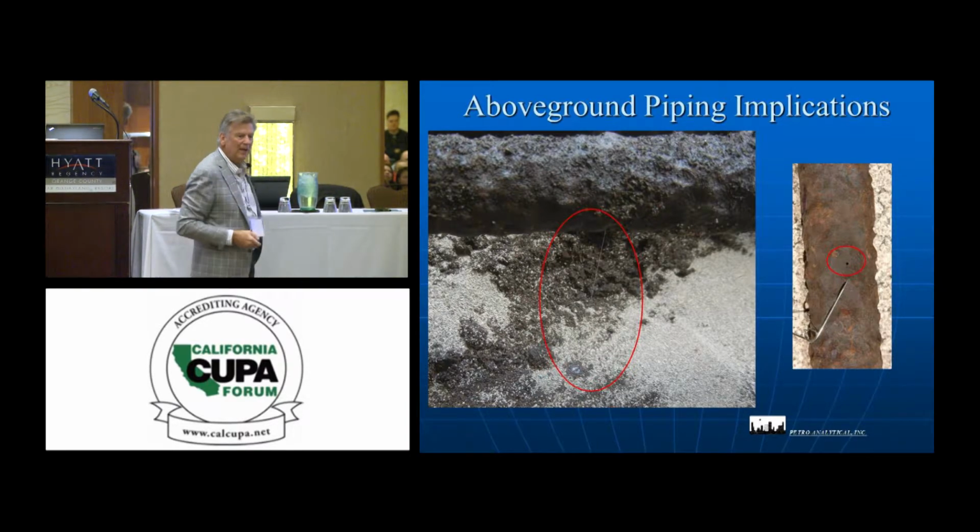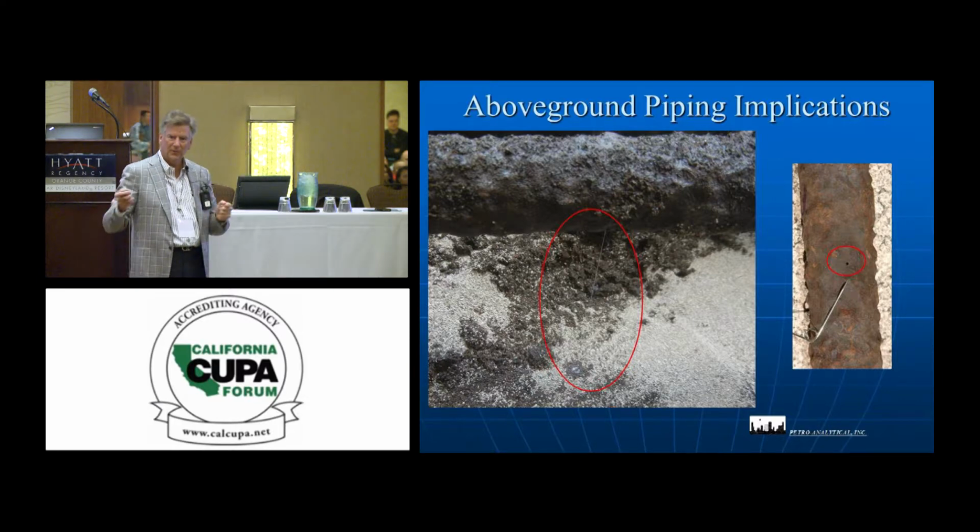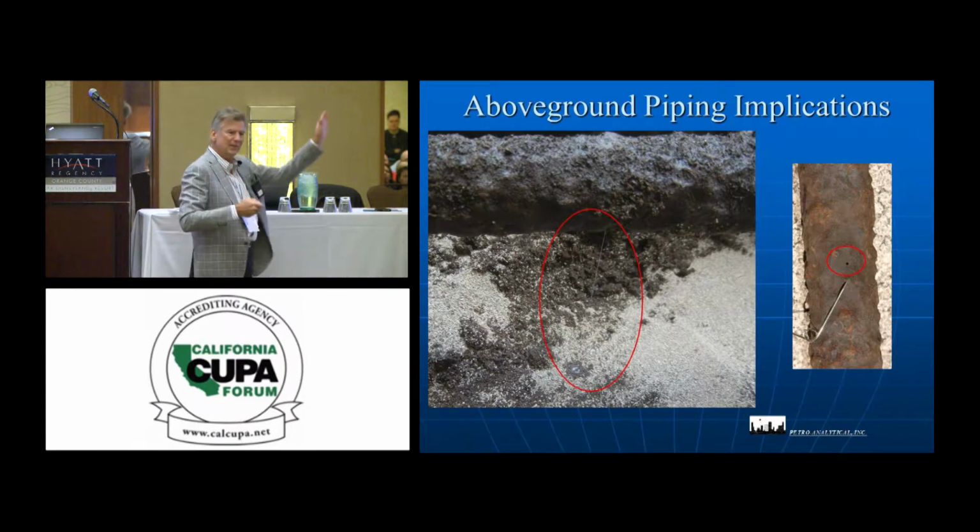So that's a live leak in real time occurring in an old above ground pipe that was in a trench under a grate that, you know, who knows, real close. Another year, and a pressure system. I mean, you can literally see the pressure. Can you see that in the back? Can you just sort of see the outline of the fuel coming down? It's extraordinary.